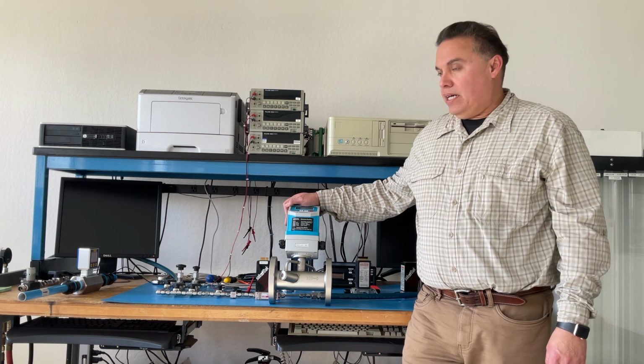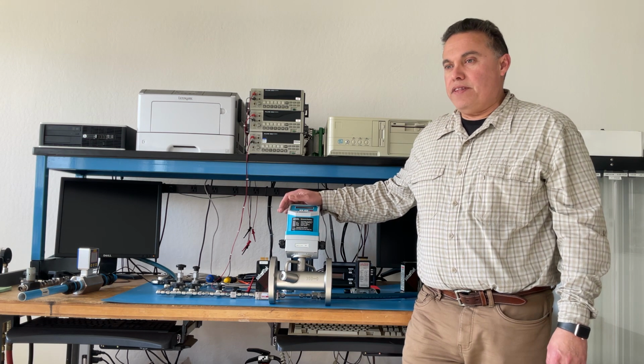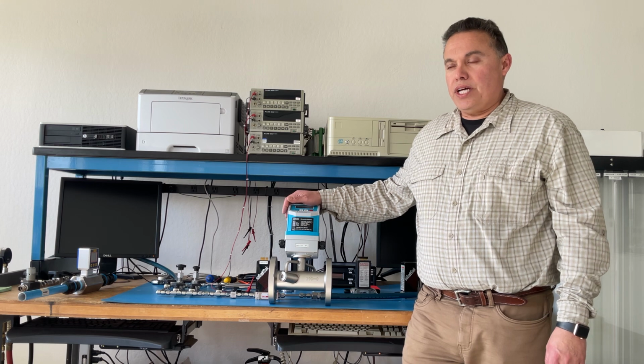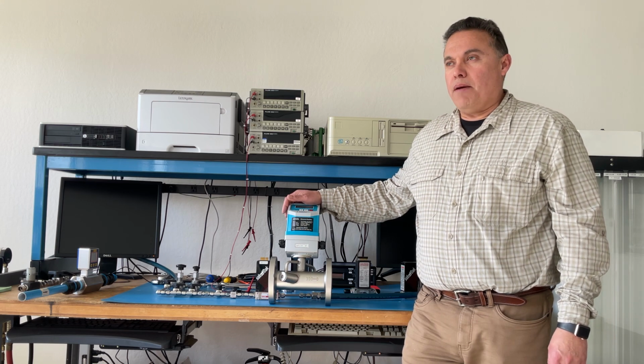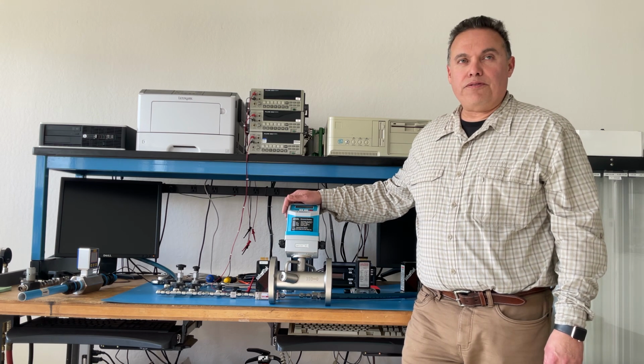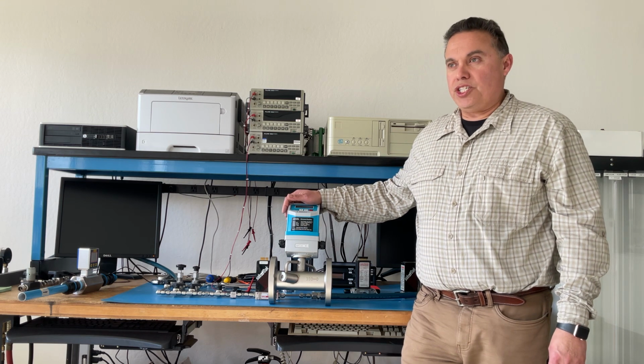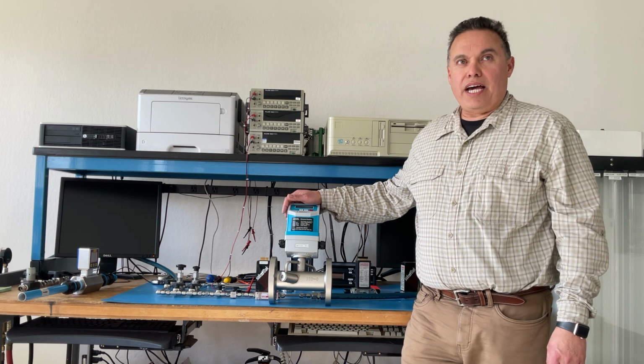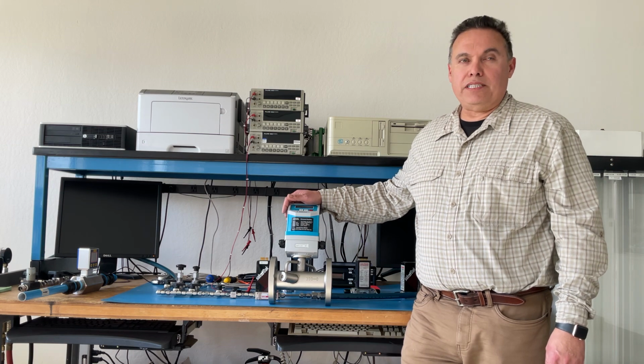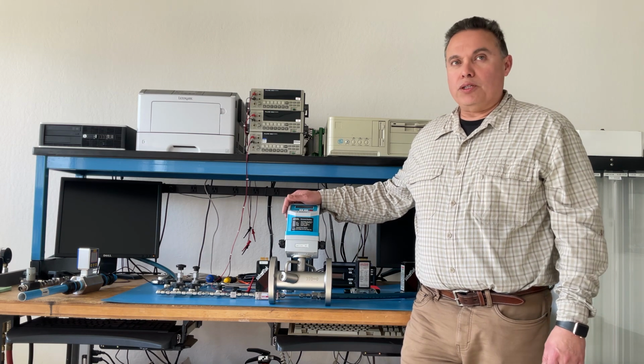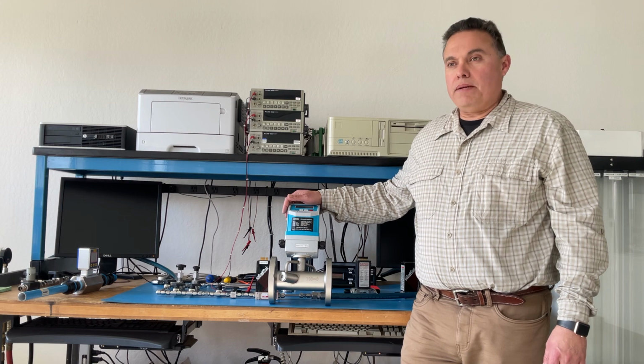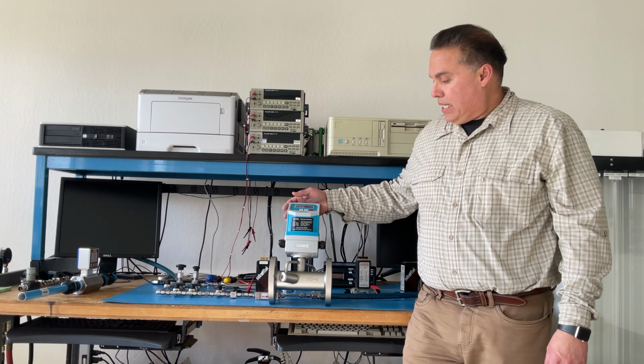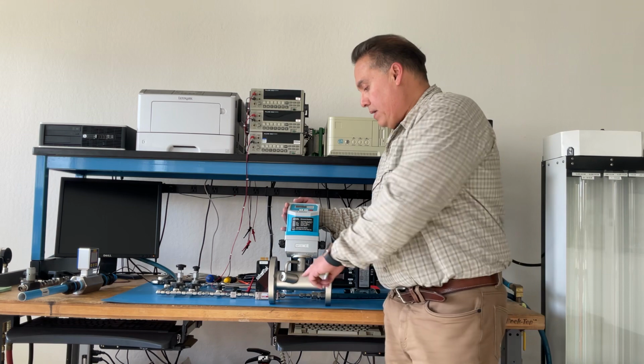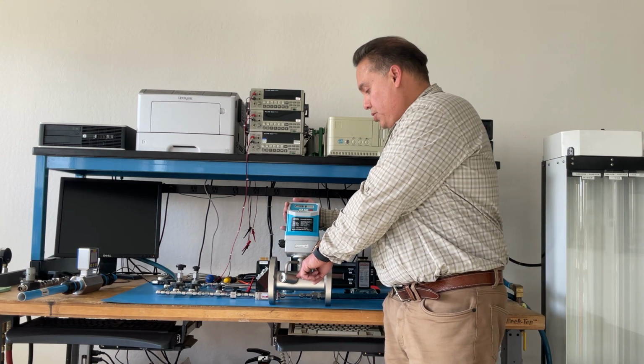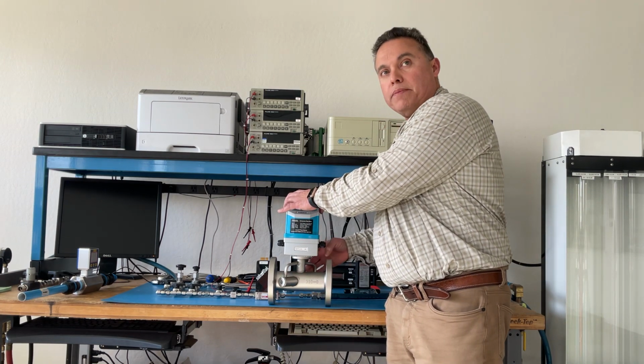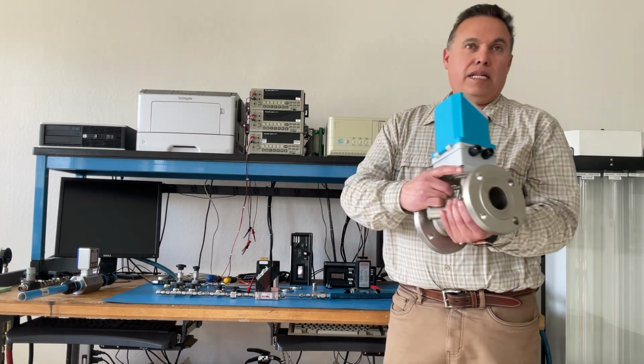That's correct. So the enemy of this particular meter is to have non-homogeneous type fluids. So if you have something that is chunky inside of the fluid, it won't measure all that well because it'll block the ultrasonic beam. It's a 1 megahertz ultrasonic beam that gets emitted from this transducer to this transducer in the back. And you just measure the amount of sound coming out the other side.